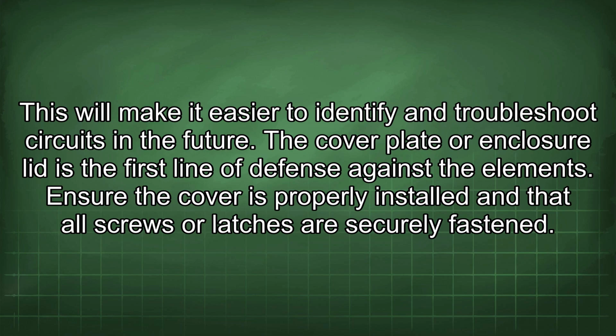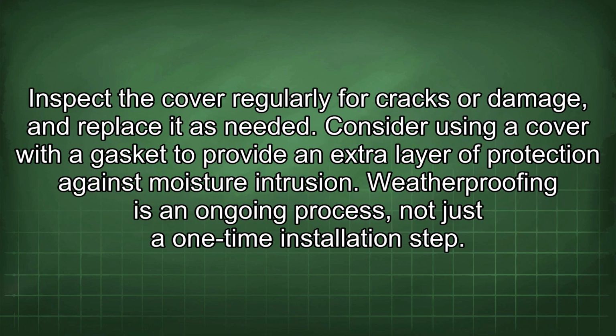The cover plate or enclosure lid is the first line of defense against the elements. Ensure the cover is properly installed and that all screws or latches are securely fastened. Inspect the cover regularly for cracks or damage and replace it as needed. Consider using a cover with a gasket to provide an extra layer of protection against moisture intrusion.